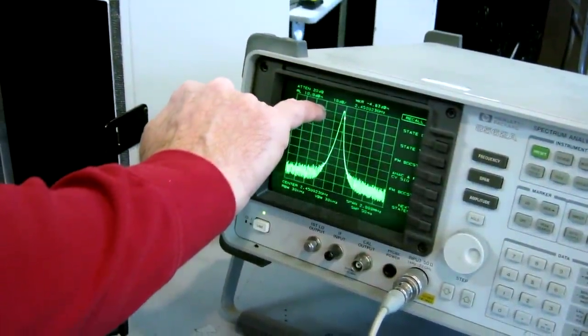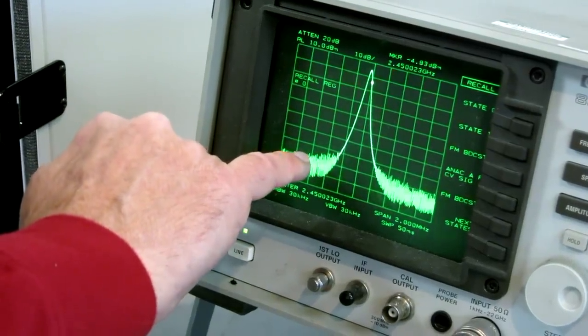And then as we measure down, 10 dB, 20, 30, 40, 50, 60, 70, 80. And you'll see our noise floor is down at about 80 dB.